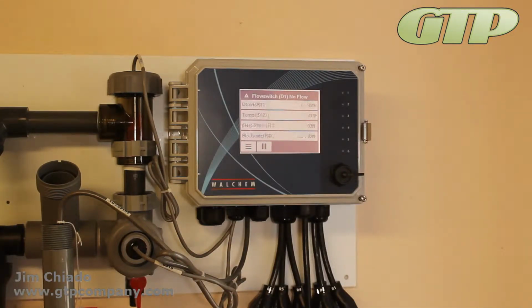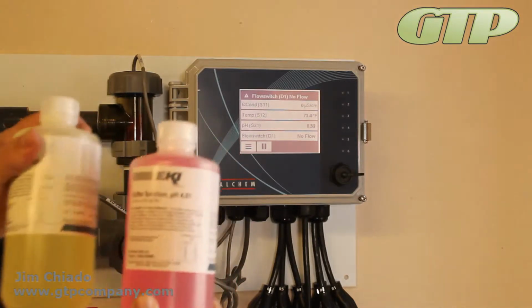pH is way more necessary to make that slope predominant. You want to make sure and give it a proper slope. So that's why they recommend a 2-point calibration. And you really should do a 2-point calibration to the side of the pH which you normally are on. Say if it's always a little acidic, you would be below 7 in a normal fashion. So you really should do 4 and 7.